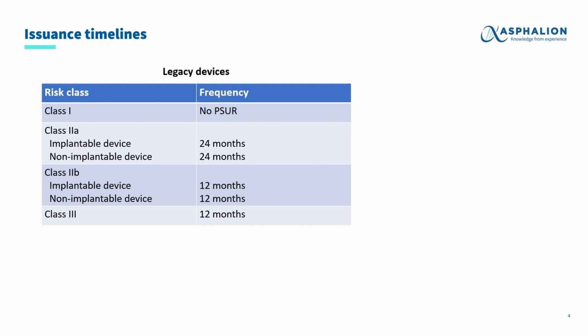So, according to Article 86 of the Medical Device Regulation, manufacturers of Class 2 and Class 3 must prepare a PSUR for their devices, and concretely for Class 2A medical devices, a PSUR should be prepared at least every 2 years, while for Class 2B and Class 3 medical devices, a PSUR must be issued at least annually. Therefore, only manufacturers of Class 1 medical devices are exempt from PSUR preparation.